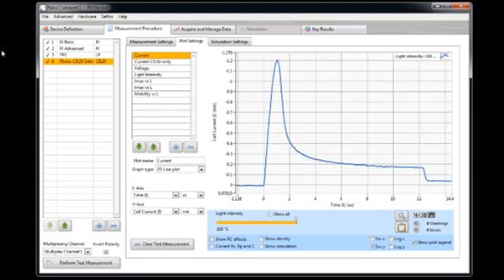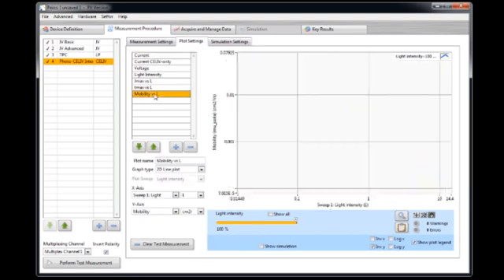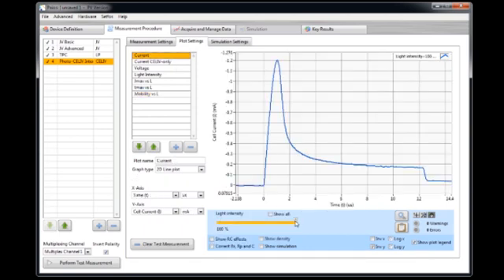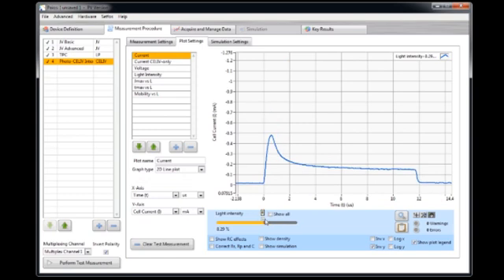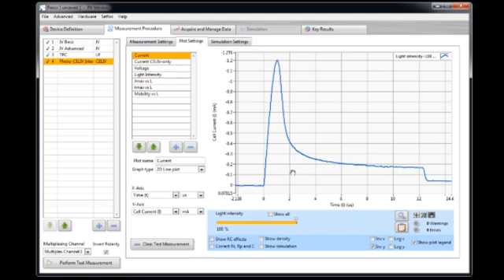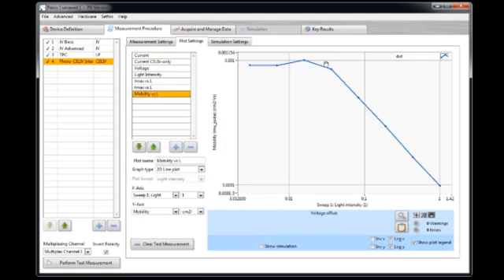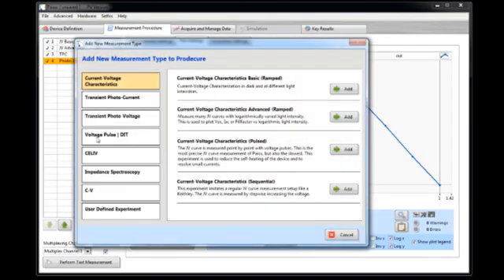CELIV measurements are frequently used to measure the charge carrier mobility. And PIOS also does some automatic mobility calculations. This is based on this position here of this current peak. And we now here can plot the mobility versus the light intensity. So you see here the mobility is constant to a certain part. And with increasing light intensity the mobility is decreasing or seems to be decreasing. This is because here the peak moves a bit to the right when the light intensity increases. And this is just due to the fact because more charge is extracted and that takes a bit more time. So in this case here this mobility in this range here would be the good one.